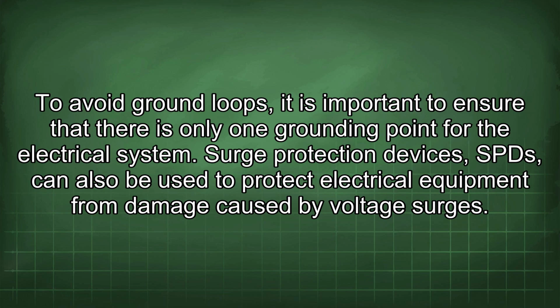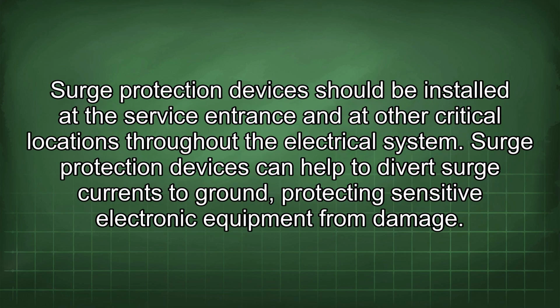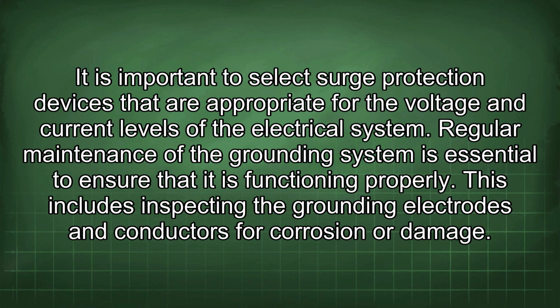Surge protection devices, SPDs, can also be used to protect electrical equipment from damage caused by voltage surges. Surge protection devices should be installed at the service entrance and at other critical locations throughout the electrical system. Surge protection devices can help to divert surge currents to ground, protecting sensitive electronic equipment from damage. It is important to select surge protection devices that are appropriate for the voltage and current levels of the electrical system.